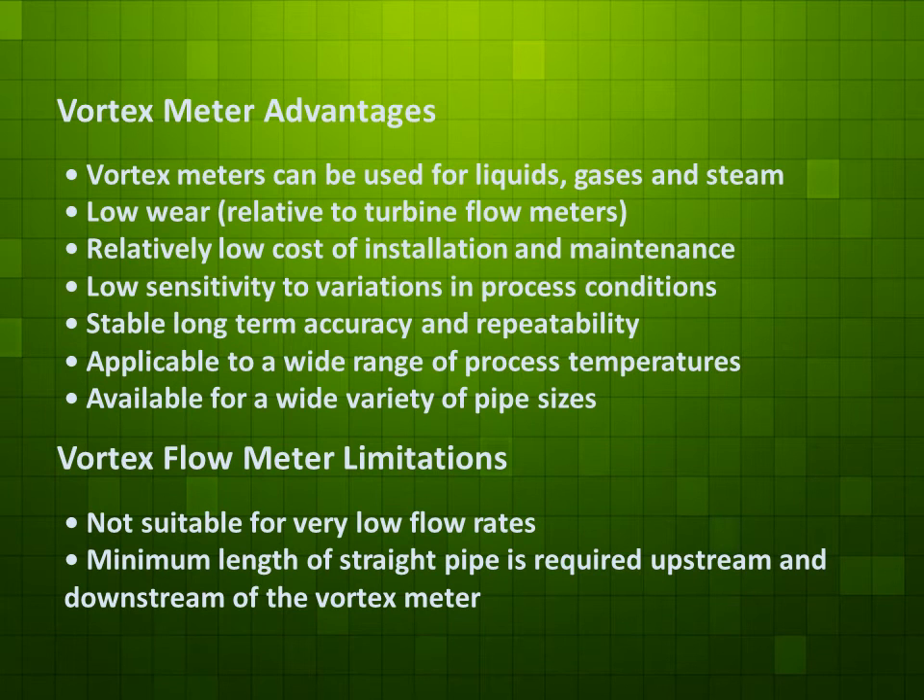Vortex meter advantages: Vortex meters can be used for liquids, gases, and steam. Low wear (relative to turbine flow meters). Relatively low cost of installation and maintenance.